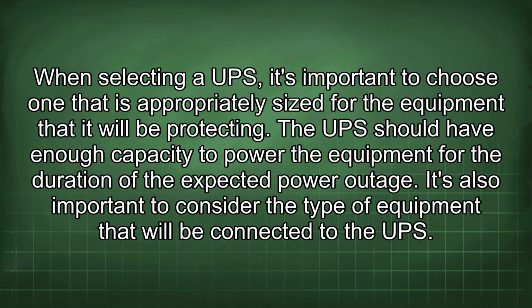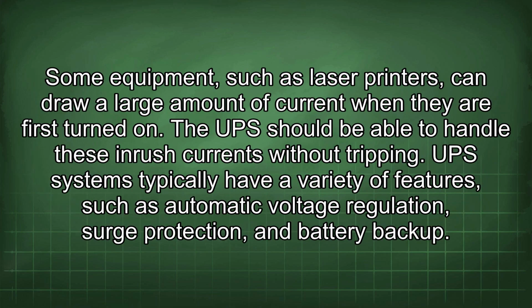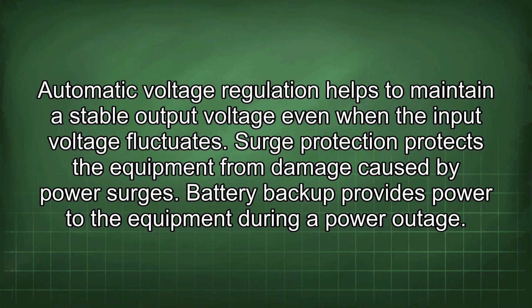The UPS should have enough capacity to power the equipment for the duration of the expected power outage. It's also important to consider the type of equipment that will be connected to the UPS. Some equipment, such as laser printers, can draw a large amount of current when they are first turned on. The UPS should be able to handle these inrush currents without tripping. UPS systems typically have a variety of features, such as automatic voltage regulation, surge protection, and battery backup. Automatic voltage regulation helps to maintain a stable output voltage even when the input voltage fluctuates. Surge protection protects the equipment from damage caused by power surges. Battery backup provides power to the equipment during a power outage.